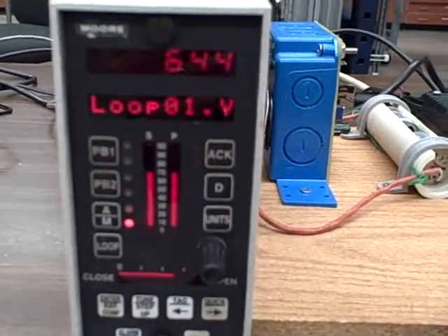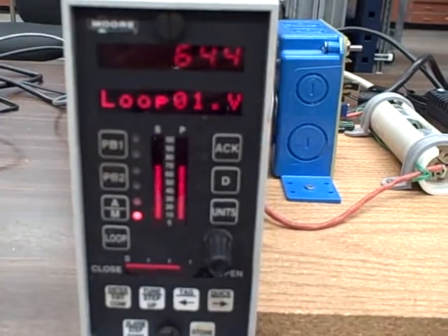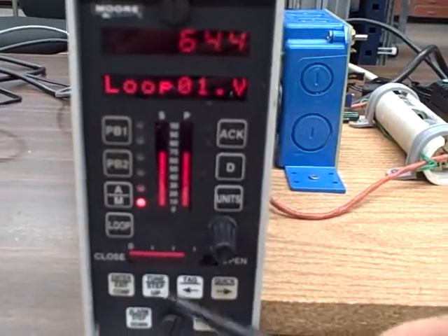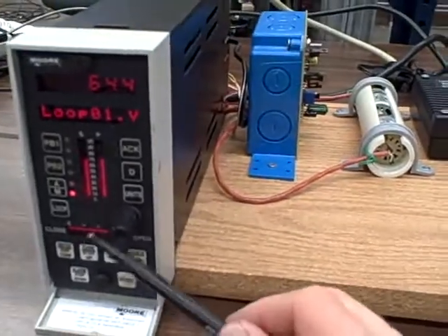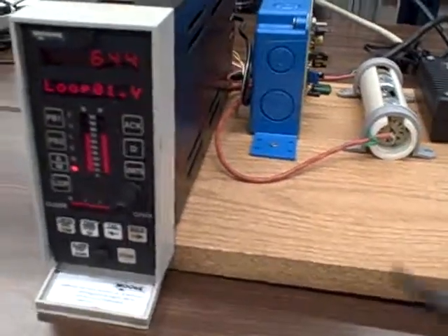Conversely, if I had hit the auto manual button at the point where the output was saturated high, I would have been left with the motor running full speed. So you've got to be kind of careful to stabilize a loop by jumping into manual mode. It's often quite a bit better to stabilize a loop by switching your gain back to a lower value. That's a quick demonstration of the effects of the proportional or gain setting on the stability of a loop, like a motor speed control.